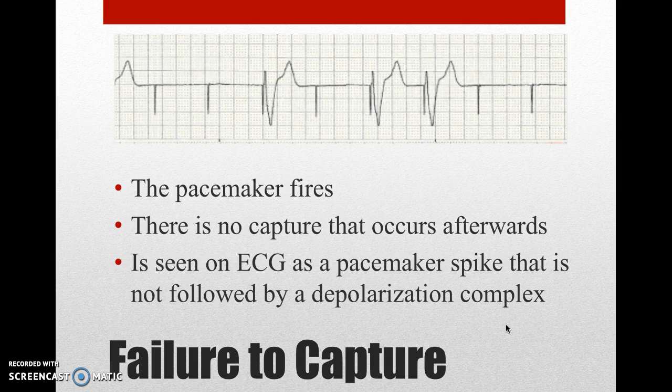In failure to capture, the pacemaker fires, but there is no capture that occurs afterwards. It is seen on the ECG as a pacemaker spike that is not followed by a depolarization complex.